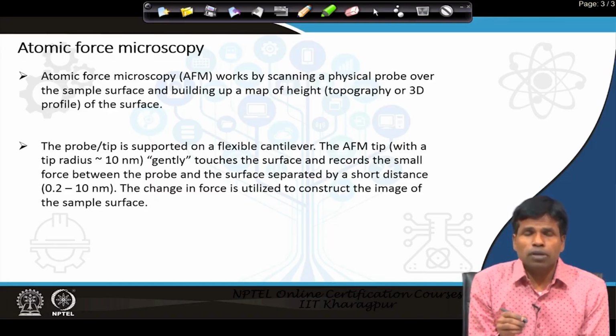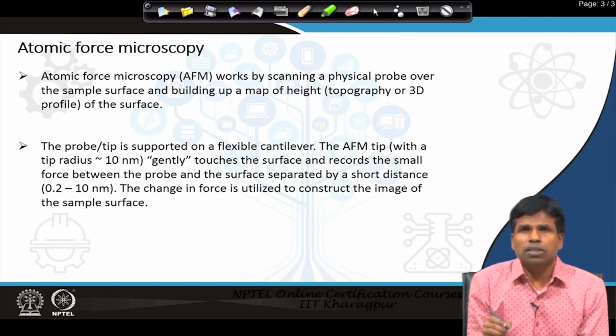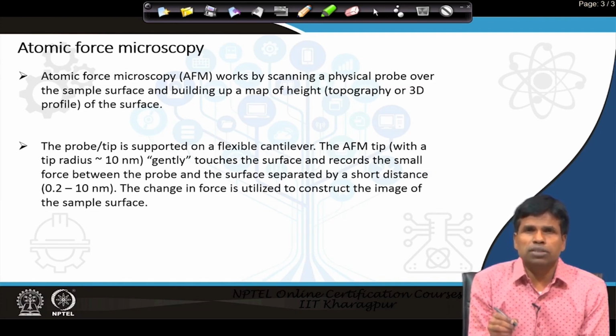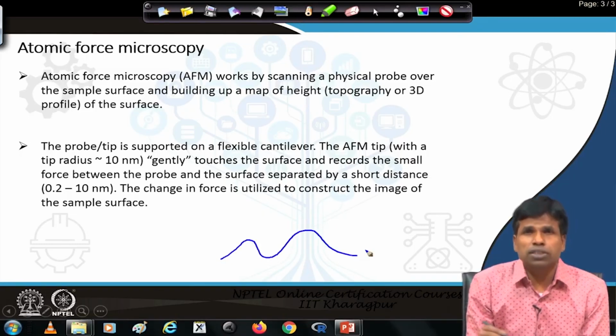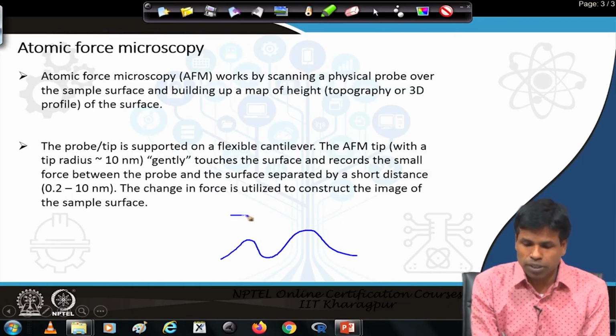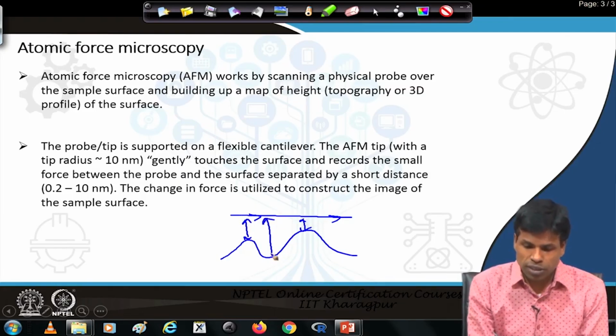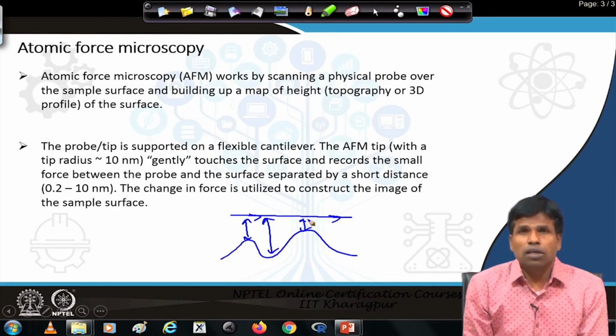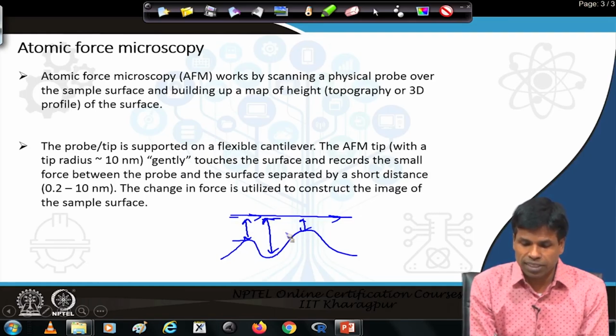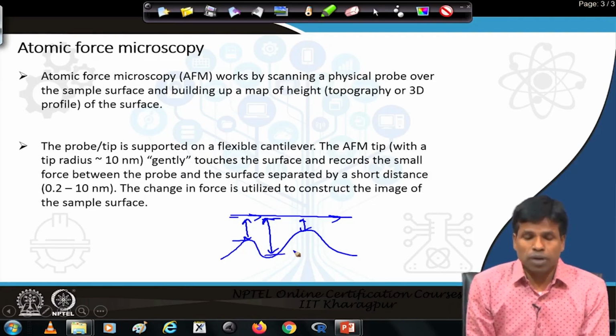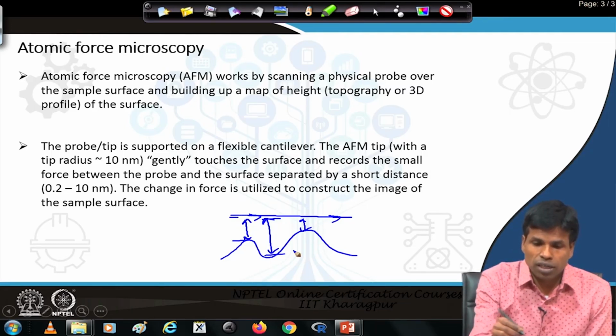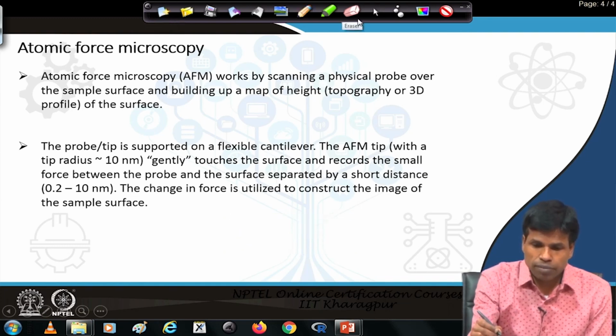Like if we have two different materials on the surface, the force between the tip and one material will not be the same as between the tip and the other material. Similarly, if the sample has roughness, then when the tip is scanned above the sample, the force at different locations will no longer be the same. So, by measuring the different forces at different locations, we can construct an image showing where there is a small gap between the sample and tip, and where there is a large gap. In this way, by measuring the force, we can create a 3-dimensional image of the sample using the atomic force microscope.